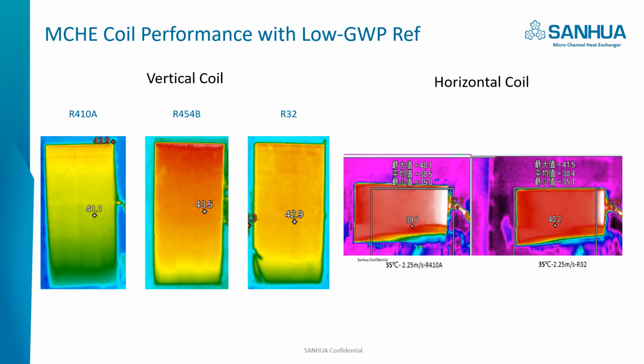This slide shows the refrigerant distribution characteristics in the vertical coils and horizontal coils. In the vertical coils, the refrigerants come in at the top and come out at the bottom, and with different refrigerants there's no big difference, and the thermal picture looks quite uniform. For the horizontal coils, there are two circuits. The refrigerant comes in from the top and then comes out at the bottom. Also, for R32 and R410A, there's no big difference.